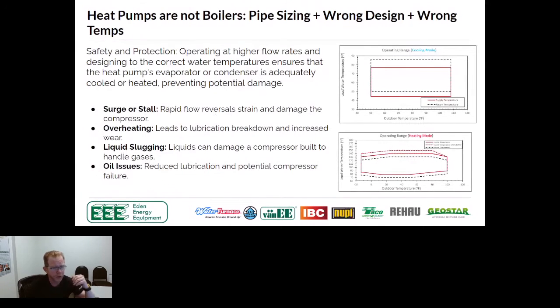So as we look at it, we talked earlier about what does it mean if we actually were to underpipe it? What happens if the actual water is not leaving the unit as quick as it should be? I've got 2 nice little graphs on the right-hand side that are showing what the envelope looks like for the operating range for heating and cooling. And so if you look at the dotted lines, the black dotted lines, this is kind of the area we want to keep you in on an air-to-water. We call that the safety buffer zone. So at 120 degrees, an air-to-water heat pump is going to work really, really good. And even if you were to push that up to 130, which is the solid red line, the heat pump's still going to do okay.